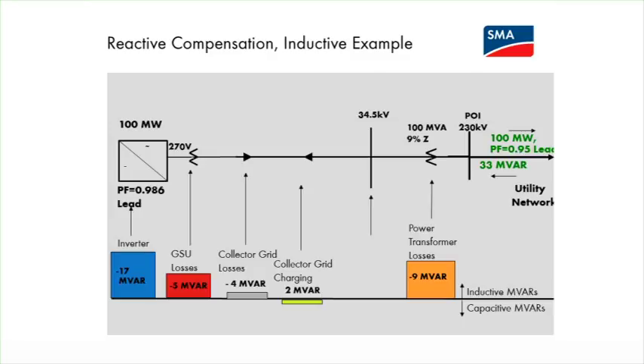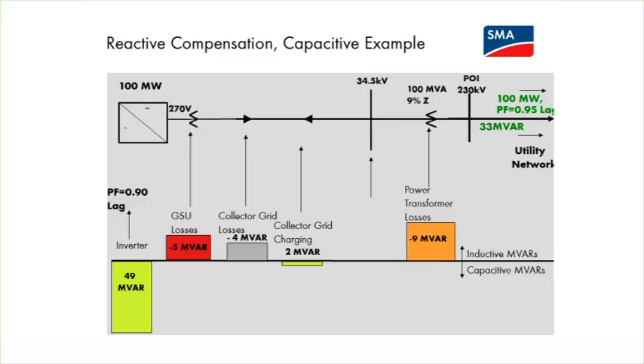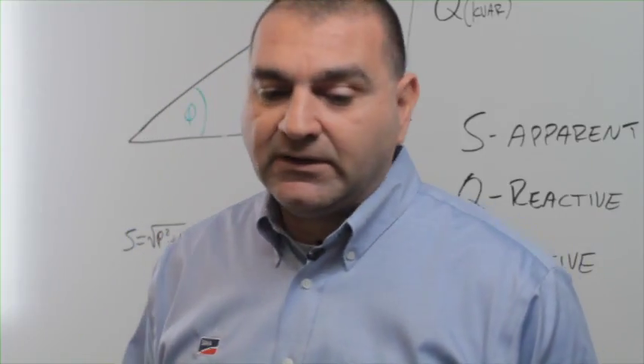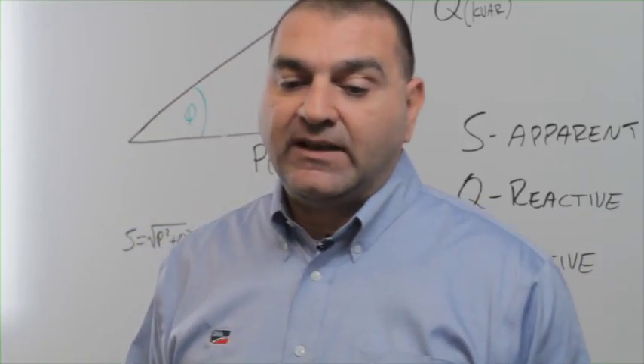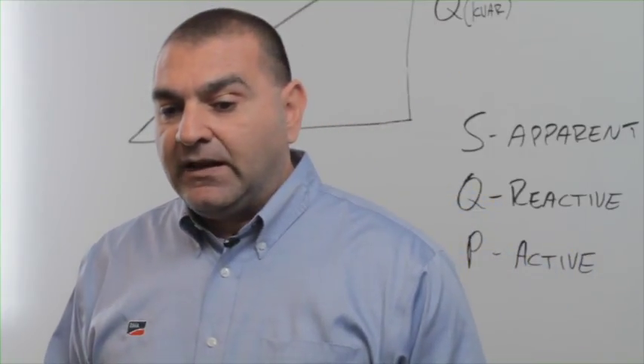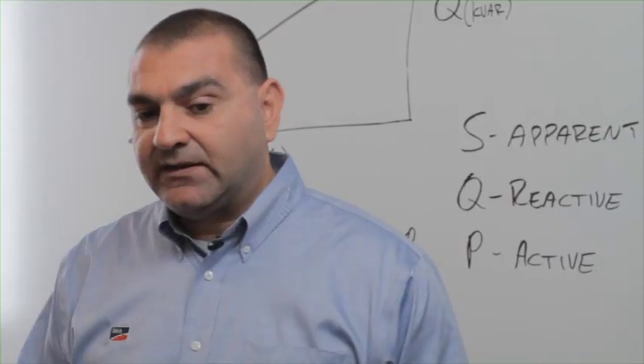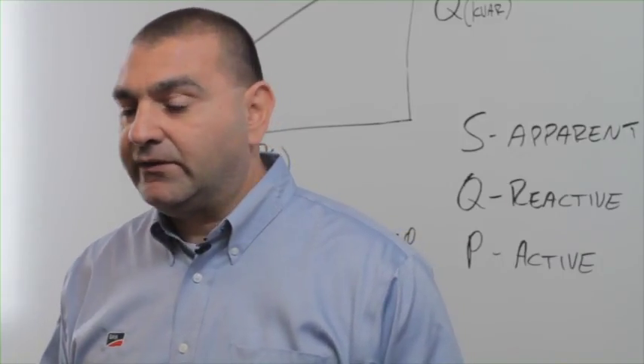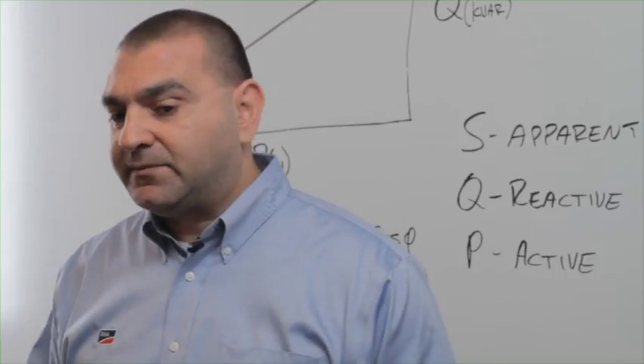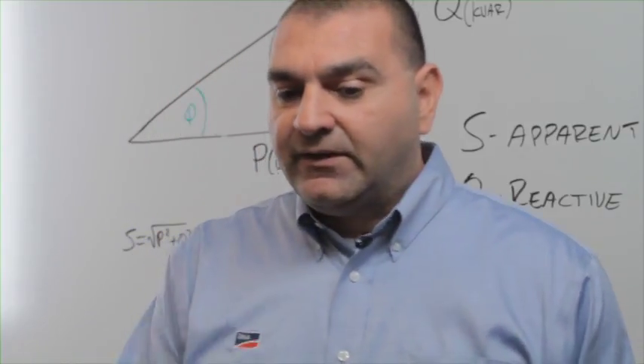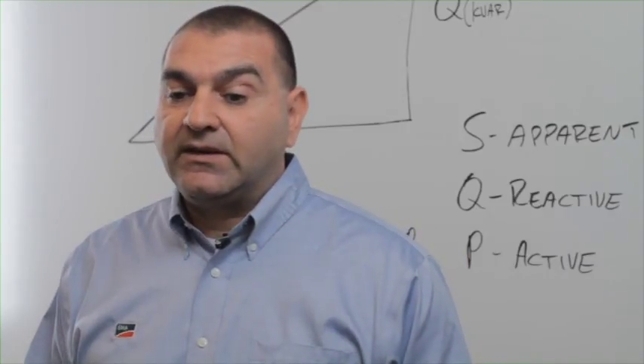that requirement. Similarly, if I'm using a capacitive example, a 100 megawatt 0.95 lead power factor, that means I have to provide 33 megawatt of reactive power at the point of interconnection. If I work through the math, then I'm supposed to be providing 0.9 lead power factor at the inverter level, which in this particular example translates into 49 megawatt of reactive power from the plant. Now, of course, there are options that you can run this with a unity power factor and buy what we call DVARs or STATCOMs or add capacitors, but that also increases the cost of the system. The VARs from the inverter come at no additional cost to the owner or the developer.